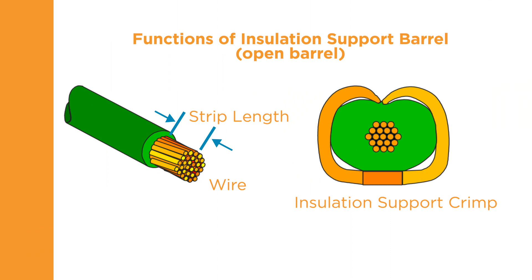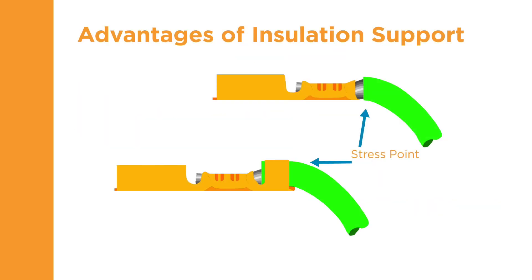The insulation support crimp forms the terminal around the wire insulation, similar to the wire barrel crimp. When crimped, the insulation support should be snug but not so tight as to cut into the insulation. The insulation support moves the stress point of the wire back from the bare wire to the insulation. The support helps protect from breakage by increasing the radius of the bend and adding the strength of the insulation to the crimp.